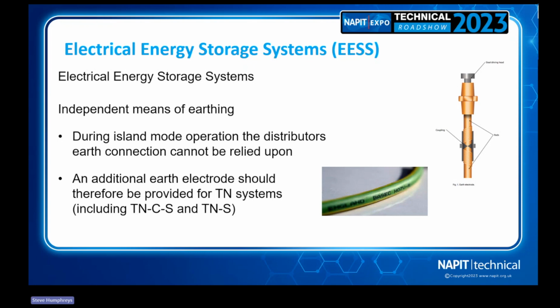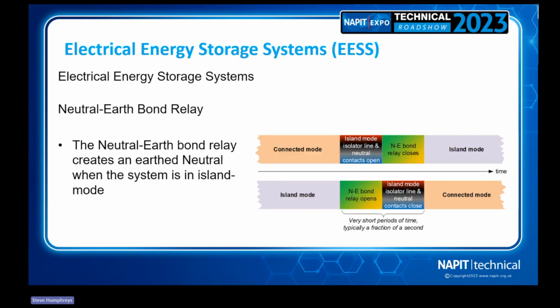So it says if we can't rely on the distributor's earth in island mode, then we need an additional earth electrode for these TN systems. If it's a TT system, obviously, and it's a stable earth electrode, below 200 ohms, then actually we can use that earth electrode as part of the system. But for TN systems, it's vital that an earth electrode, if it's capable of island mode operation, is installed.